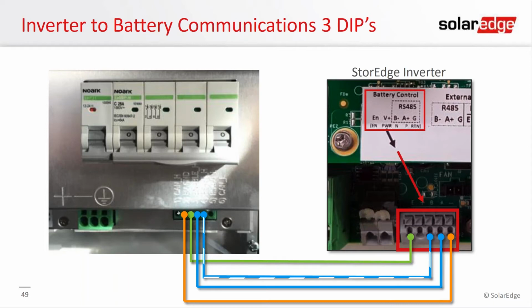So here's the wiring schematic. We're only going to be using an enable ground, enable high, enable low, and then enable shield. So basically, you just follow this wiring diagram. In some of the documentation that we supply, the quick installation guide shows you this exact diagram. So just follow it along, and this is where we connect it to the StorEdge inverter. So these little squares up here are little push terminals.